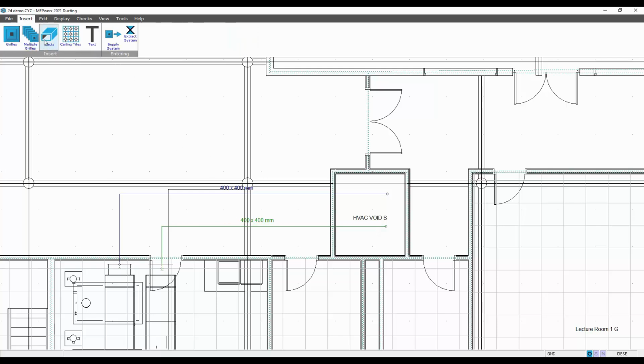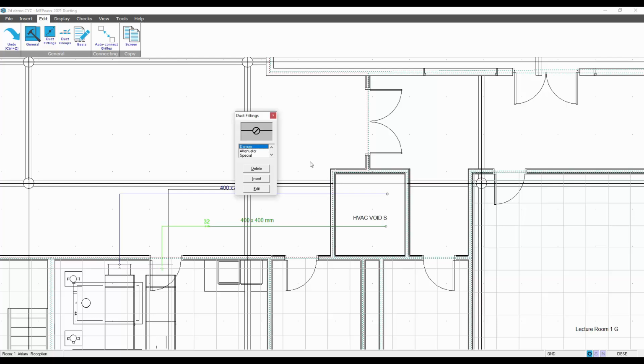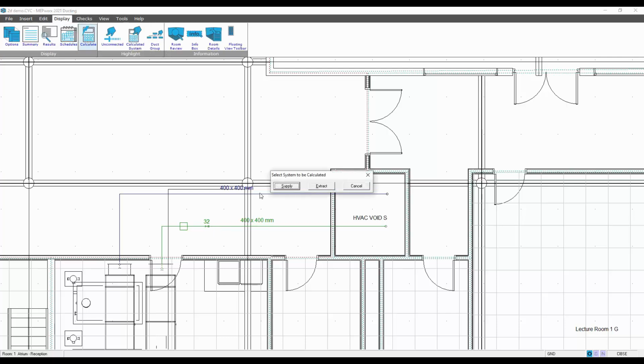So all I need to do is insert ducts, double click on the duct just to break it, making sure of course I'm on the supply menu. So I'll go to File, Insert, and make sure I'm on the supply system, and then insert a duct, double click. That breaks the duct, so I can now edit duct fitting, put a special resistance in, select the duct and apply my resistance. Well, I might want to emulate the air handling unit itself. Display calculate, and that updates the supply system.